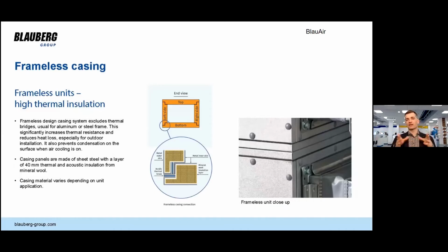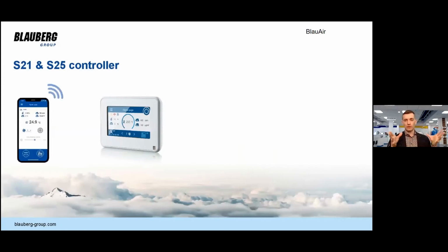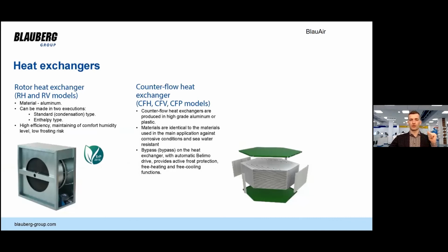The frameless casing has a unique construction where thermal bridges are excluded. The S21 control system can be controlled by mobile application, touchscreen, wall-mounted control panel, or by connecting to a building management system. Rotary or plate counterflow heat exchangers are available. Rotary heat exchangers can be made either with regular or enthalpic technology. Counterflow heat exchangers can be made from plastic or aluminum depending on the size of the unit.